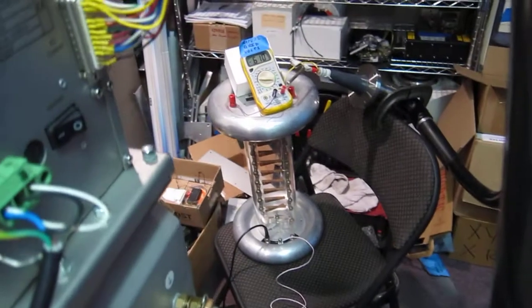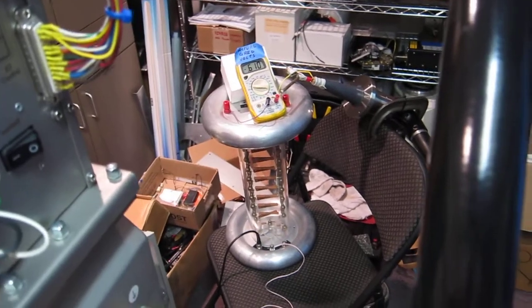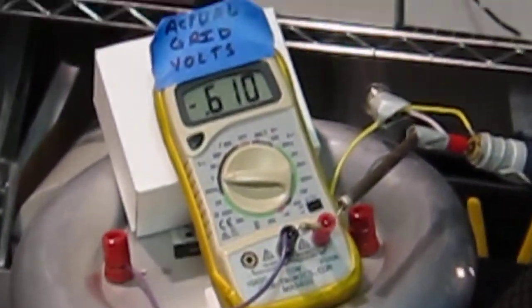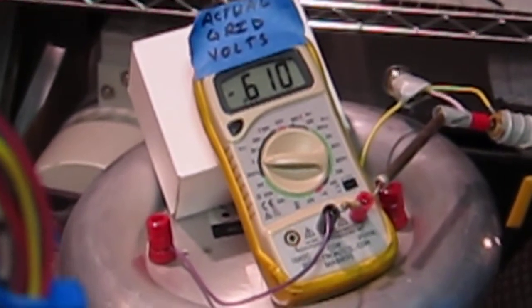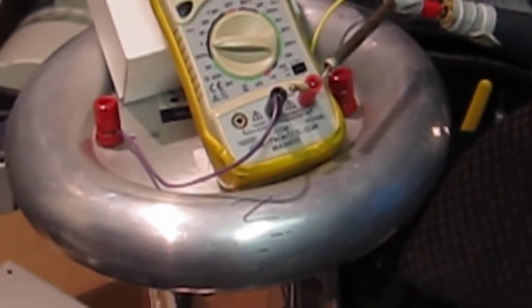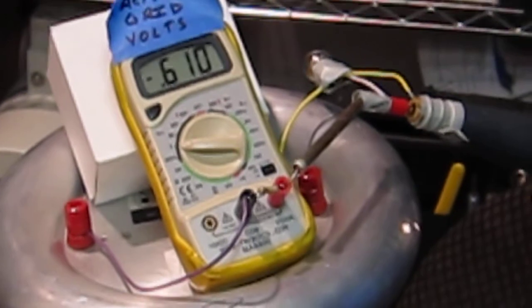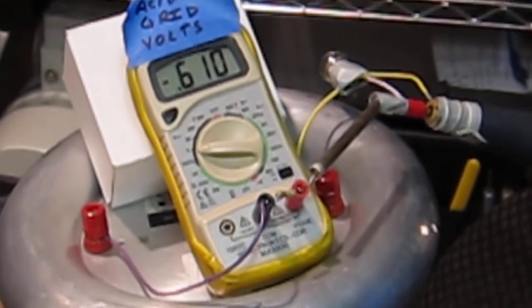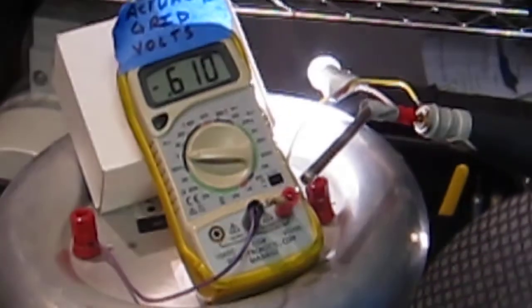Here I'm reading an output of 18 kilovolts. So over there on that terminal there is, well, now it's 20 kilovolts, 20.6 kilovolts, and the readback that requires scaling with the computer says 1.4 volts. And there you see the grid voltage has changed slightly, 610 volts. And what I can do now is increase the filament current. And pretty soon you should see the filament start to light up inside the little test lamp.